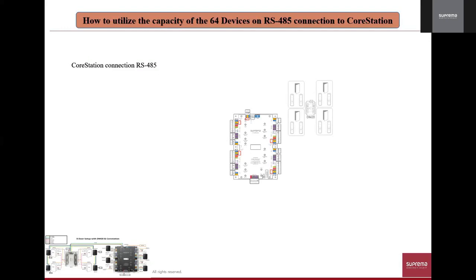All right. So if you look carefully right there, I've only done one DM20 as an extender, and I have 4 doors. In order for me to support those 4 doors, I needed 1, 2, 3, 4, 5, 6, 7, 8, 9 slave units. All right. And keep in mind, on the one RS-485 interface, I could support up to 31 slave units.